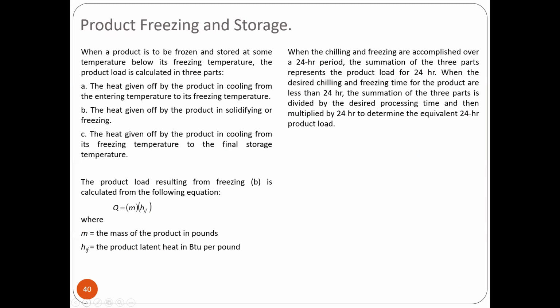Now, product freezing and storage. So, when the product is to be frozen and stored at some temperature below its freezing temperature, the product load is calculated in three parts. A, the heat given off by the product in cooling from the entering temperature to its freezing. B, the heat given off by the product on solidifying or freezing. C, the heat given off by the product in cooling from its freezing temperature to the final storage temperature.